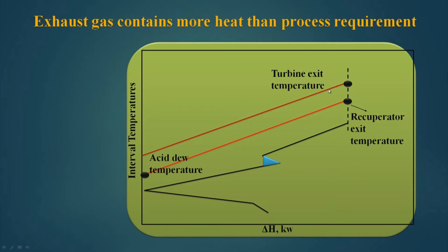To achieve this, we take up some energy from this turbine exit gas and give that energy to the recuperator. The recuperator will heat the incoming air and will bring down the turbine exit gas temperature. So there will be a fuel saving of this amount — this is the delta H axis — and the fuel saving will be worth this much of delta H.